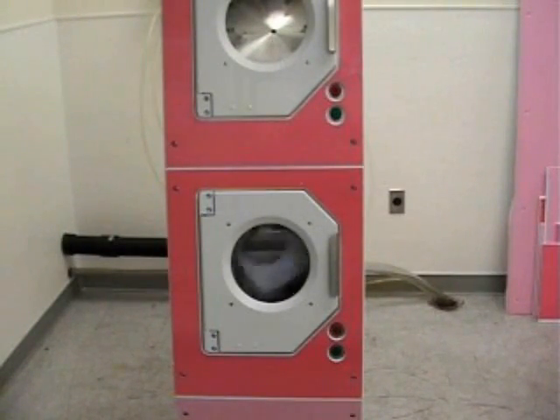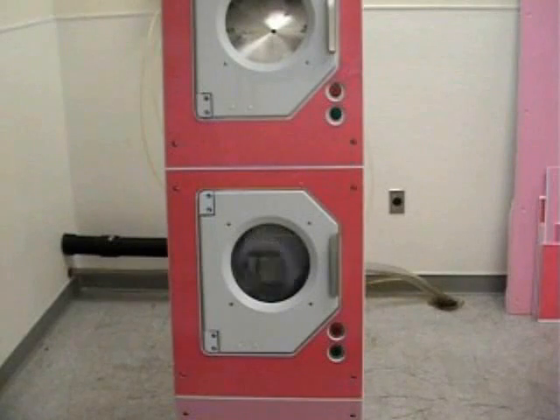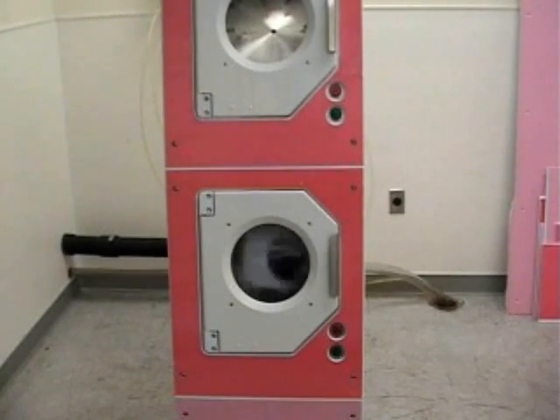The Semitool rinser dryer is set up for dual redundancy. Each head assembly and controller and power supply is independent of each other. So if you have any preventive maintenance issues, you're working on one of the rinser dryers, the second one is fully utilized. After this demo, I will go ahead and run both rinser dryers at the same time so you can see that the system processes dual cassettes, and I will do this for 2 or 3 process runs to show the system for its final quality control.